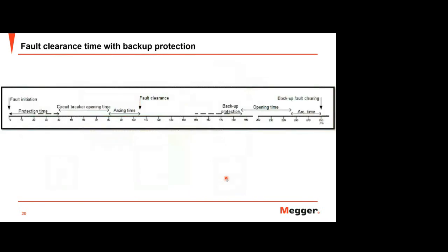Okay, and if your system has backup protection, maybe they still add some more delay until your backup protection works. It is the same until here, just different here. Some companies still consider the arcing time, because after the breaker opens, current is still flowing at some level, so they decide on some arcing time to estimate the total clearance time. And if one breaker fails to operate, they still have some spare time for backup protection to work. So in total, from fault initiation to backup fault clearing, it is around 250 milliseconds. They need to make sure the system is no more than this value. It is also a reason and benefit of this first trip testing.